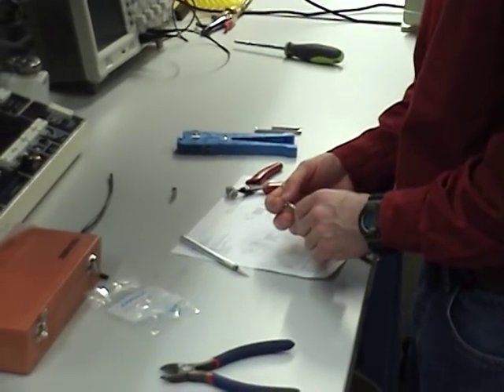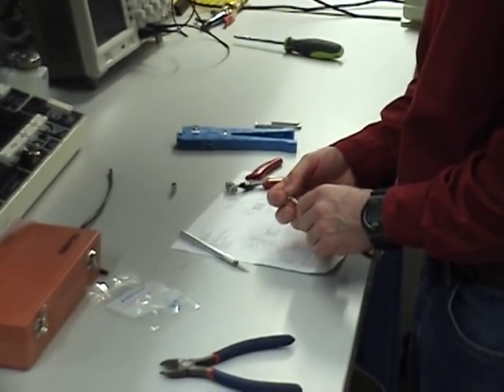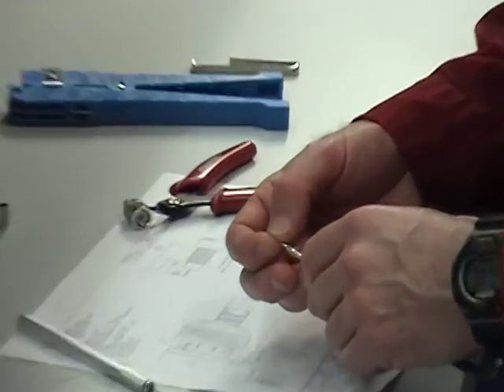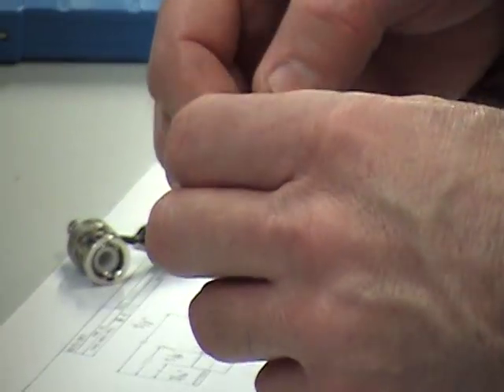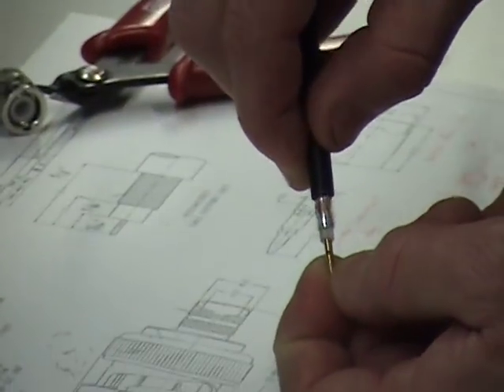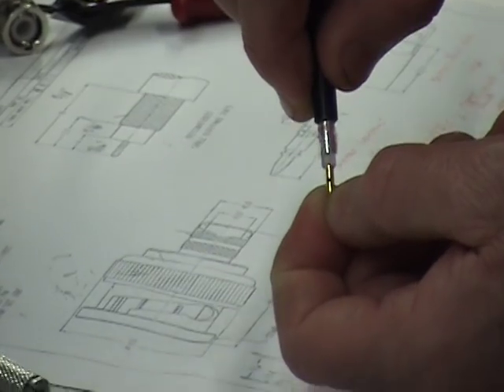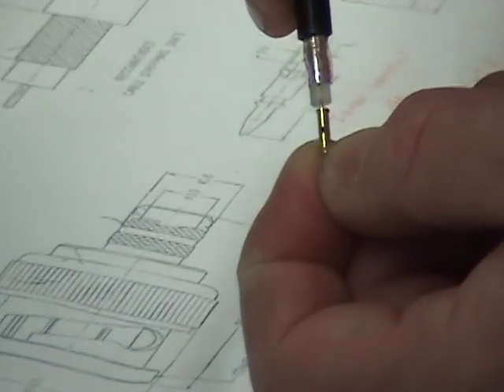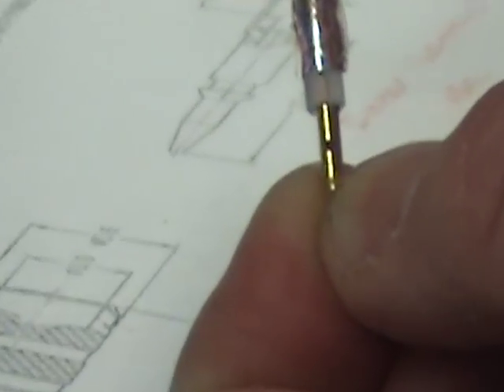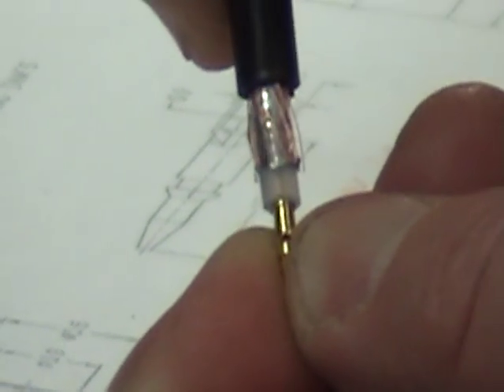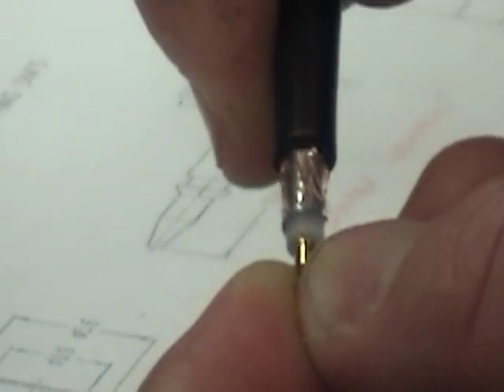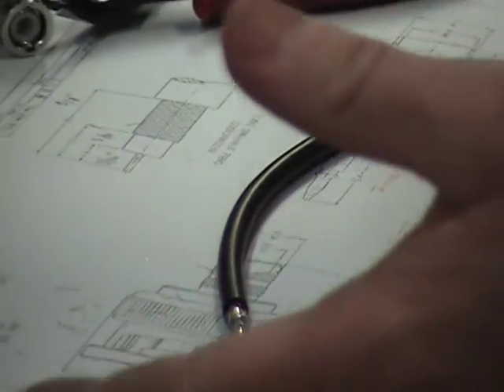That's set up to place my contact. I'm going to do the inner contact first. I lay the inner contact, then I check it. Do I see the center conductor protruding through the inspection hole? And I do. Through the inspection hole. And then I see the dielectric up against the dielectric. Perfect. That's how I want it to be. And that's how I want to make that crimp.